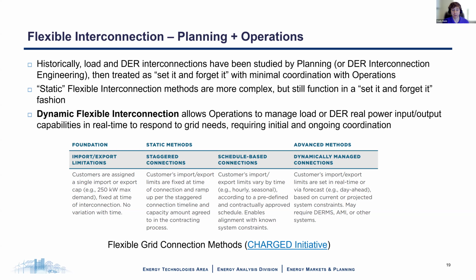So instead of making a system upgrade to prevent any bad thing from happening that may only happen 5 to 10 hours out of the year, the idea with flexible interconnection, especially dynamic, is you would send a signal to reduce the level of consumption or the level of solar production during these specific hours where things are constrained. There's a lot going on under the hood to get this to function and to be serviceable for both parties, but it is a very interesting concept that is hopefully driving improvements and less construction and more flexibility in the operating space.